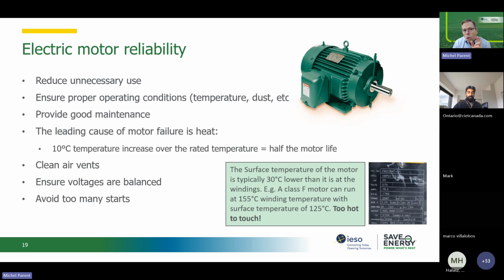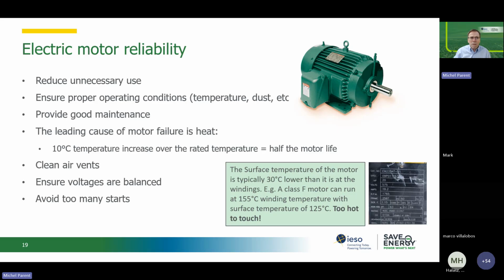Now we're going to switch to motor fans and motor pumps, because motor reliability is not about just the contactor starting the motor. It's also how you maintain that motor. Does your PM program have anything in regard with motors? From my experience, there's usually very little that is done with the actual motors in most PM programs. And sometimes for good reason, you do have limited resources. You do have to target the biggest potential issues, but you need to know a few things about motors.